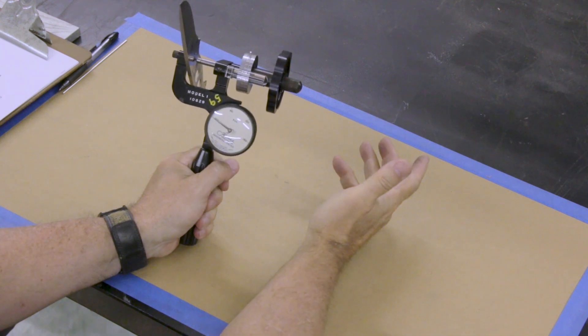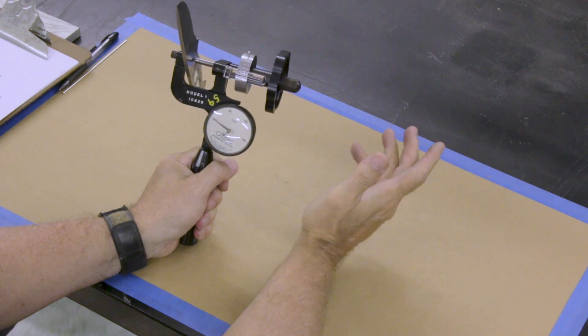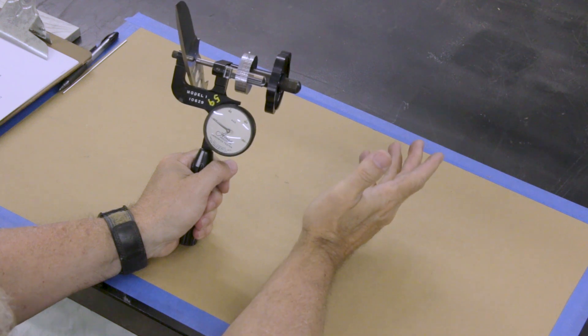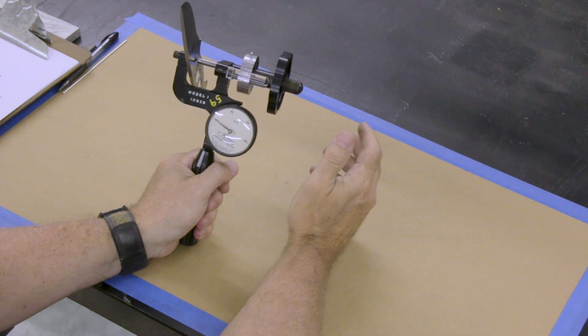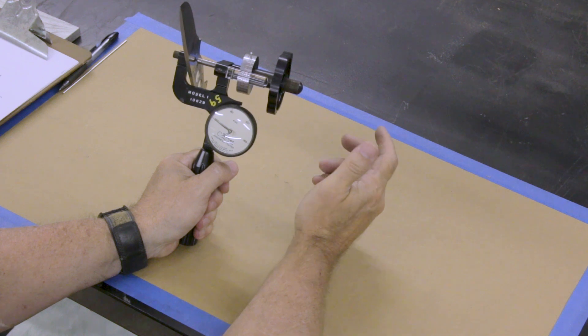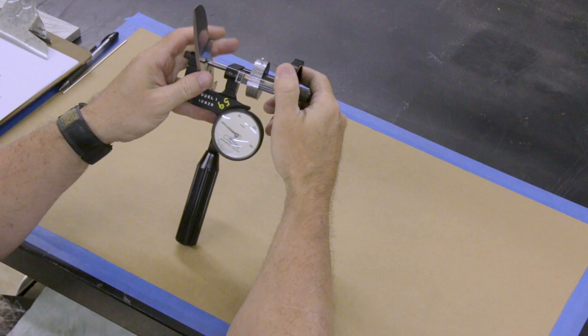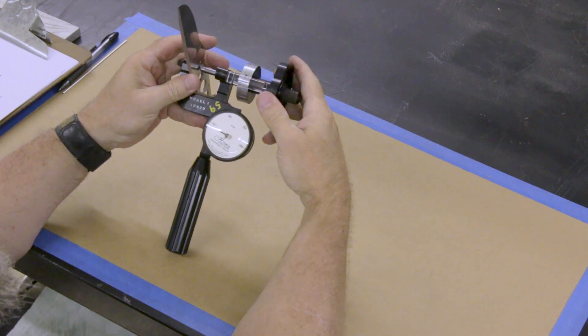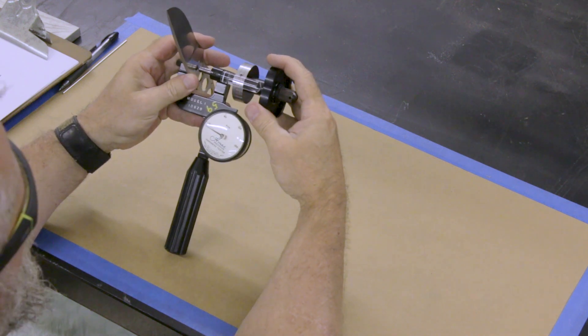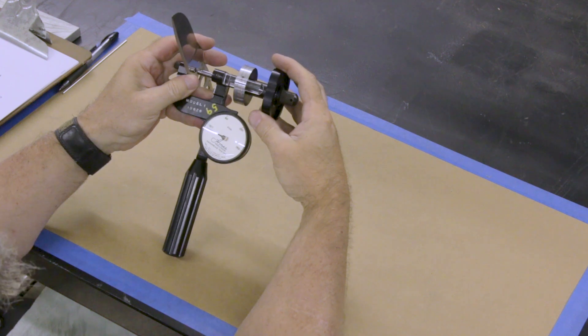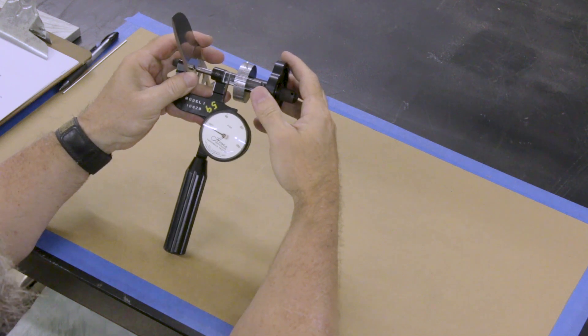Now if you recall, I know my indicator is off by 2. So this blade is probably at 62. But I don't rely on one reading. I take two or three readings and average. If I get the same reading twice in a row, I don't take a third reading.